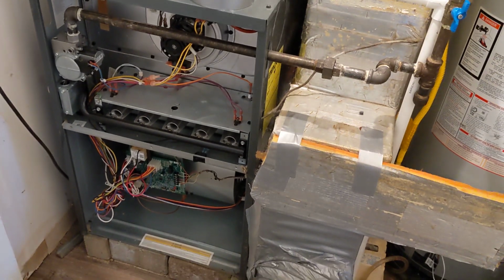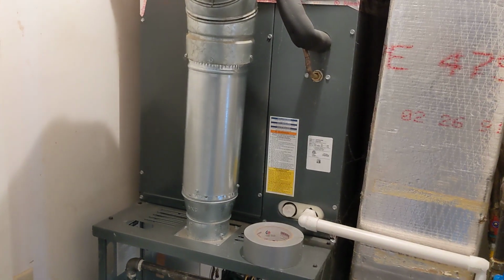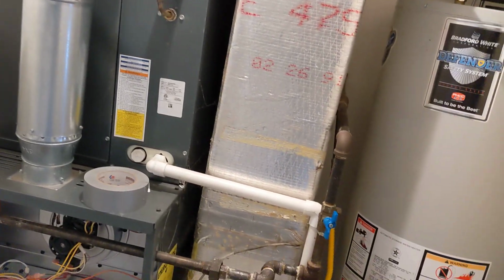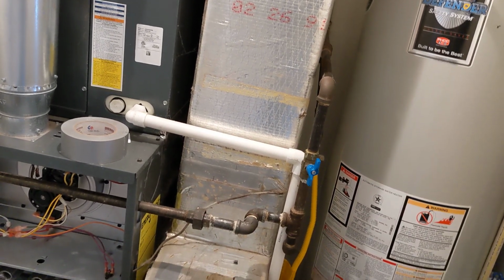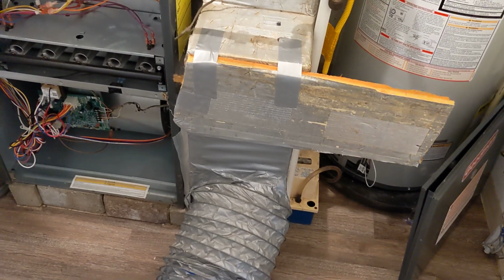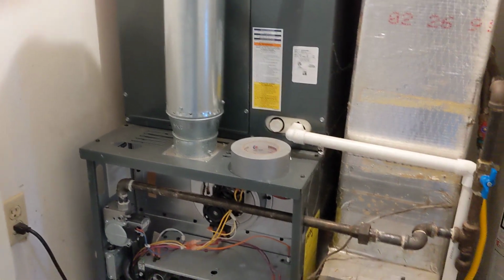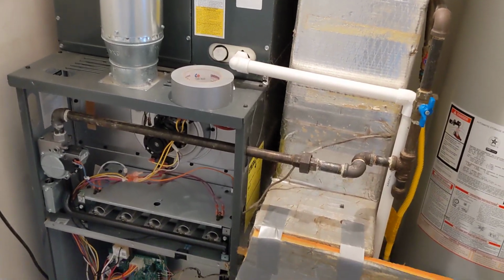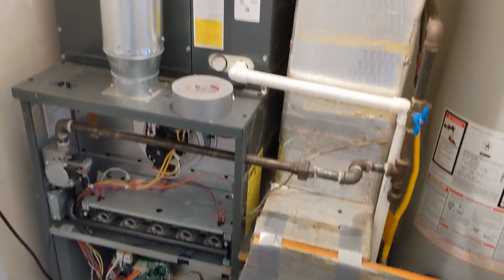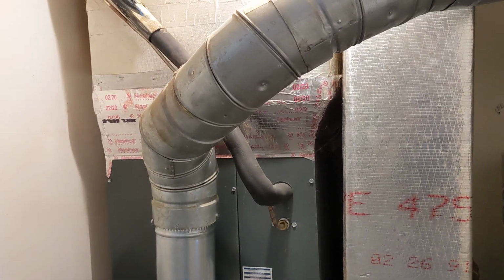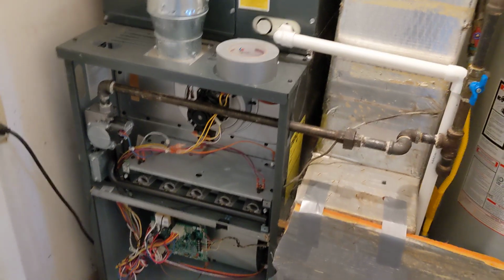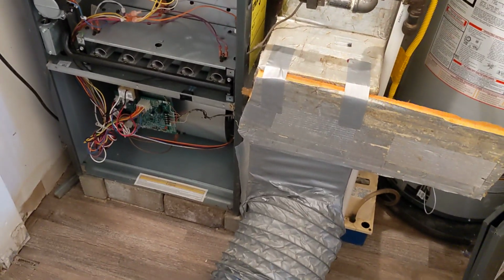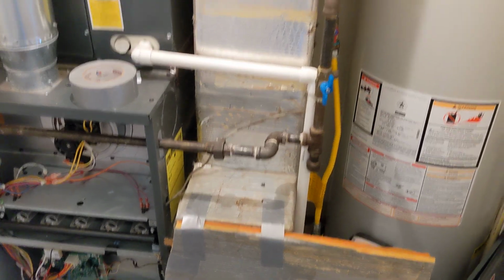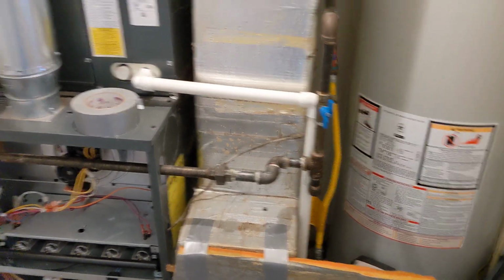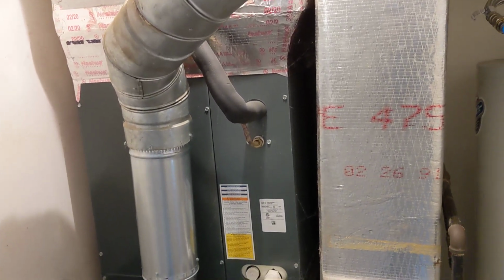The reason is if you start with the supply side and you clean everything, because the return is pulling air from the house back in and then getting filtered out and then going back into the supply. That's how the system works. It's usually functioning on 10% outside air, which means 90% of the air that's coming out of the supply is just recirculated air, typically for residentials.